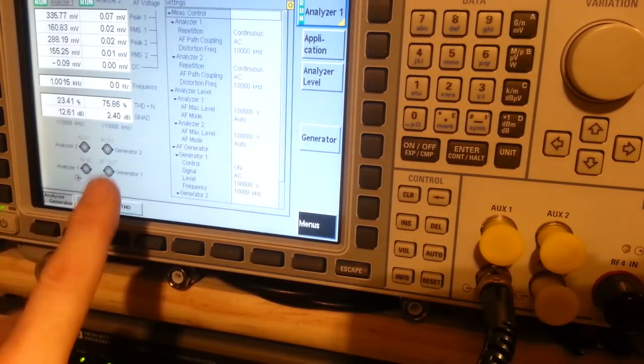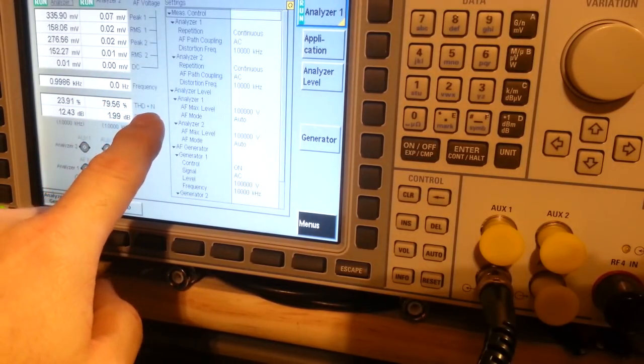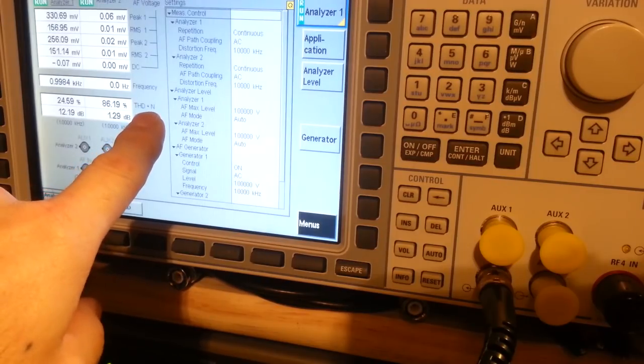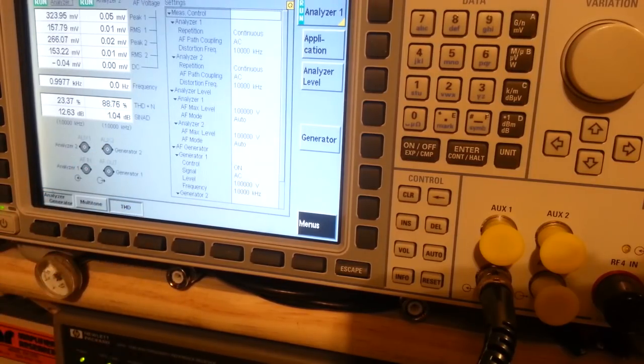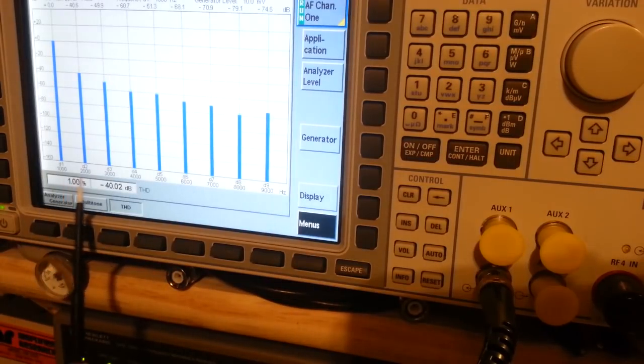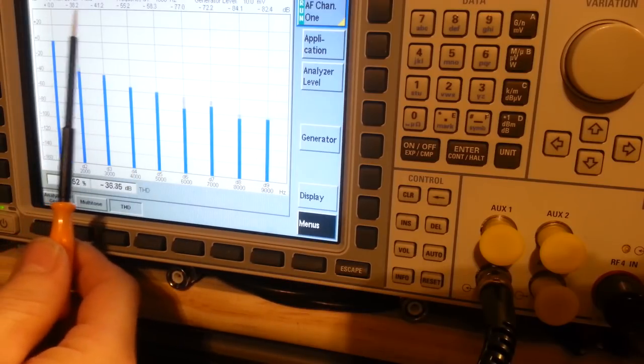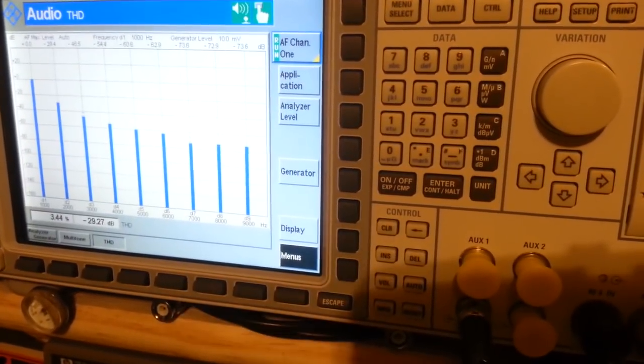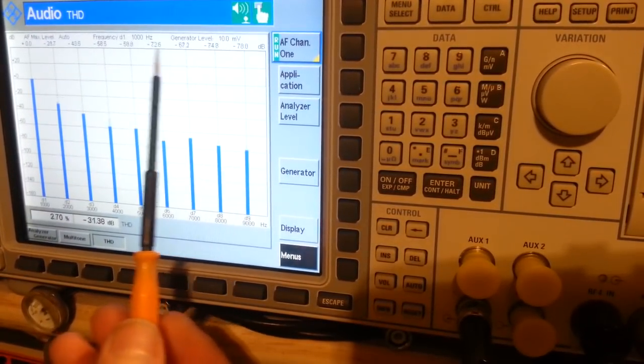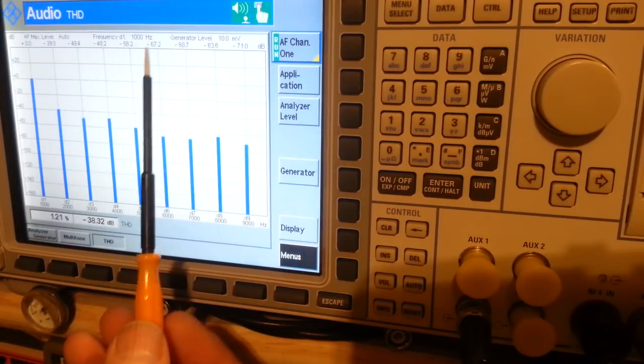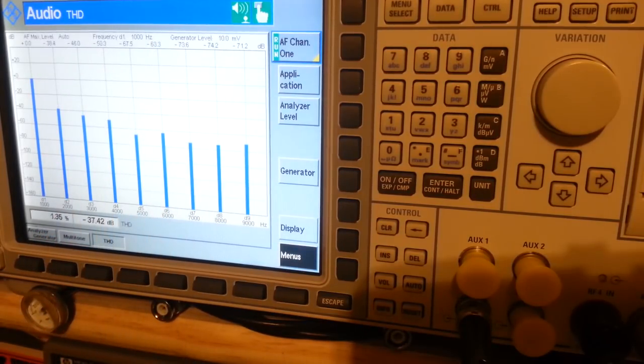THD plus noise skyrocketed because this measurement includes the magic N, or noise, where this measurement is only measuring the power at 2,000, 3,000 hertz, 4,000, 5,000, and on out to 9,000 hertz. Those are the only measurements being taken, and they're actually right up here. Move the camera up just a bit. You can actually see the actual numbers up here in dB. It's only measuring at those specific frequencies.